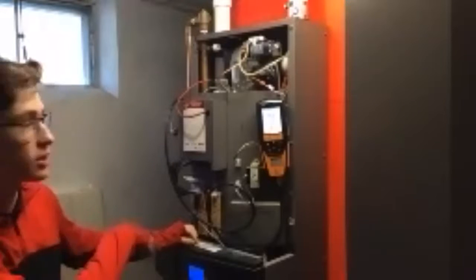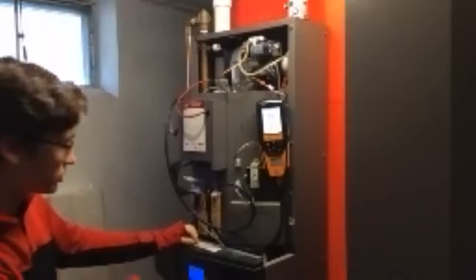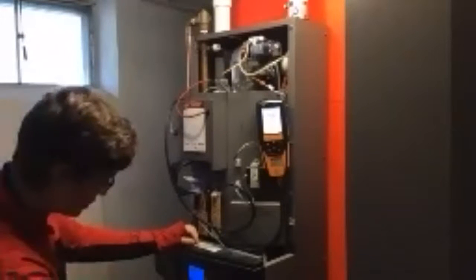Then you're just going to put your paper clip back into that hole that we found, and do one tap on that button that's down there, and the fan will start to turn off. And if you press this button that says end, that takes out the service mode.